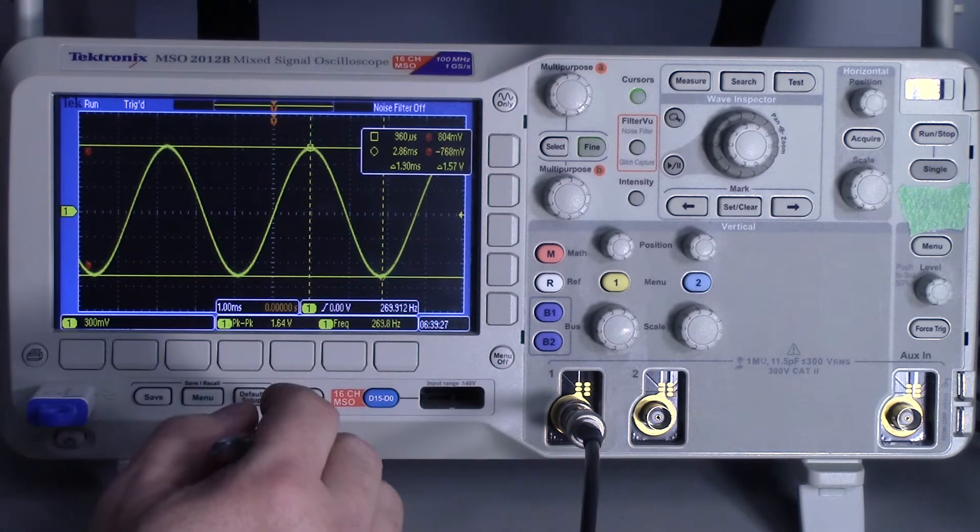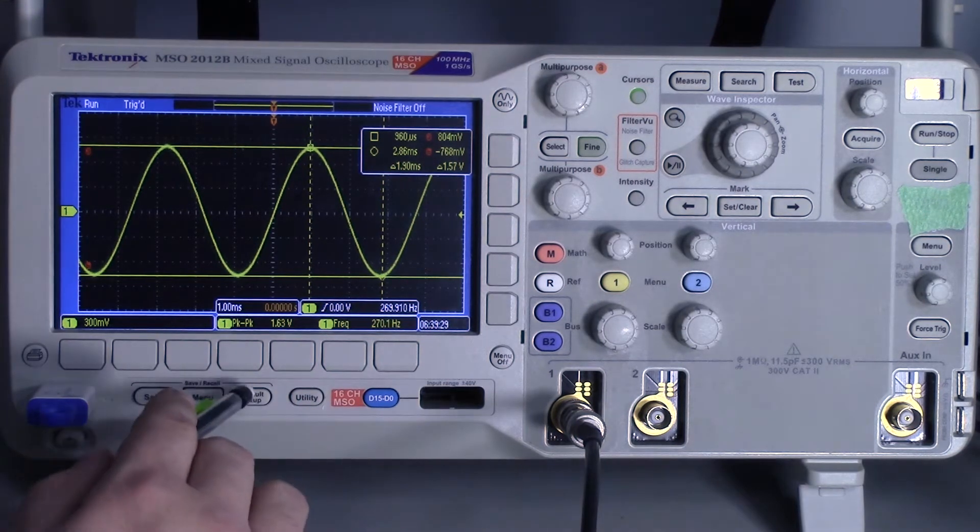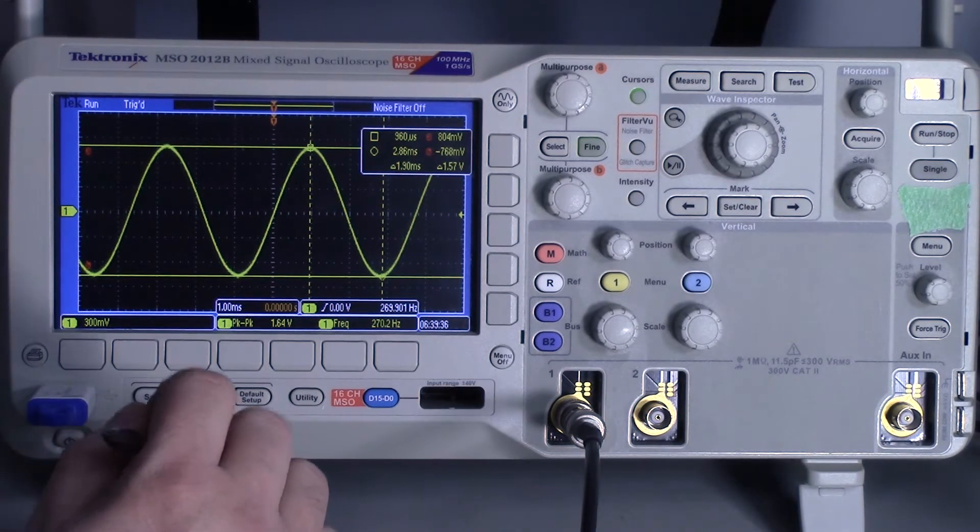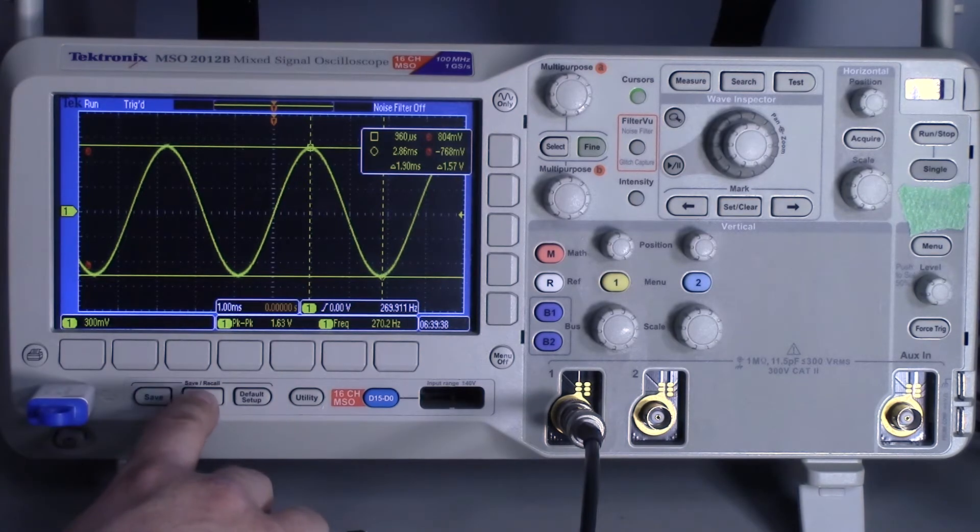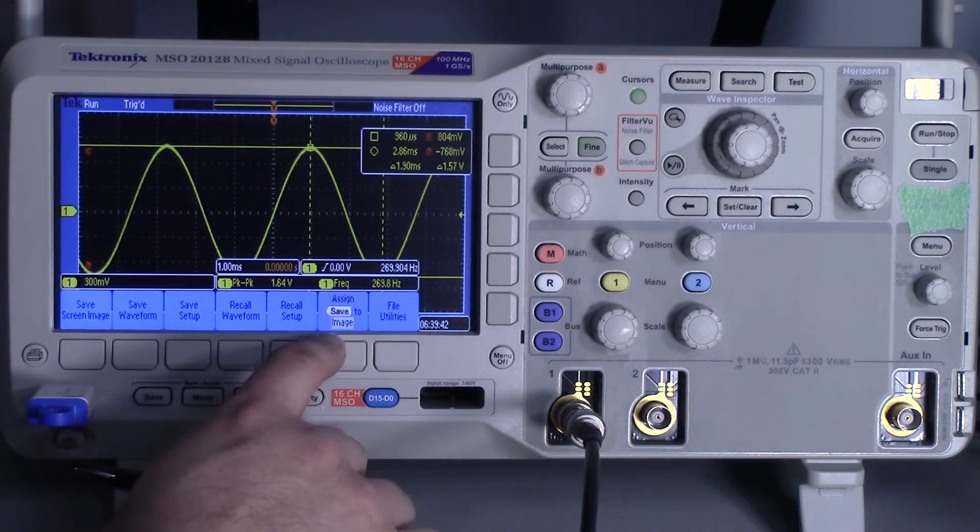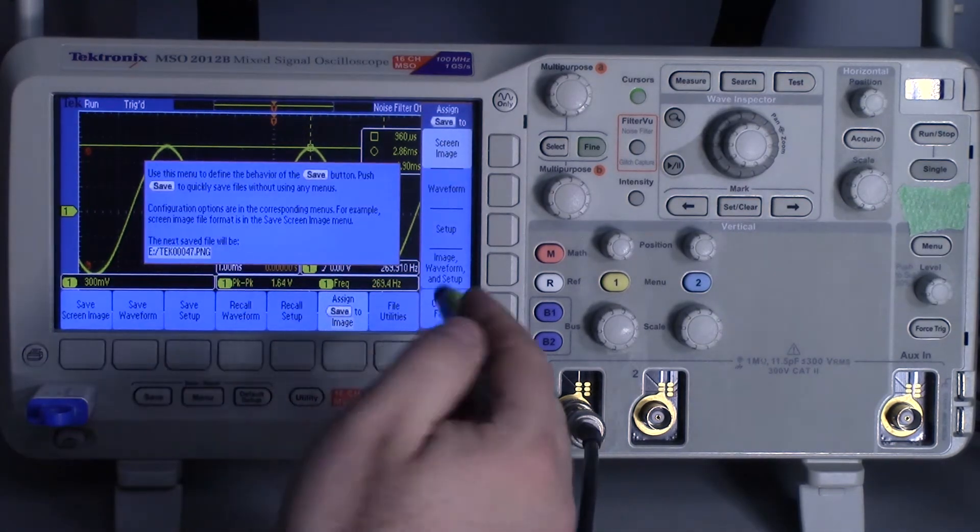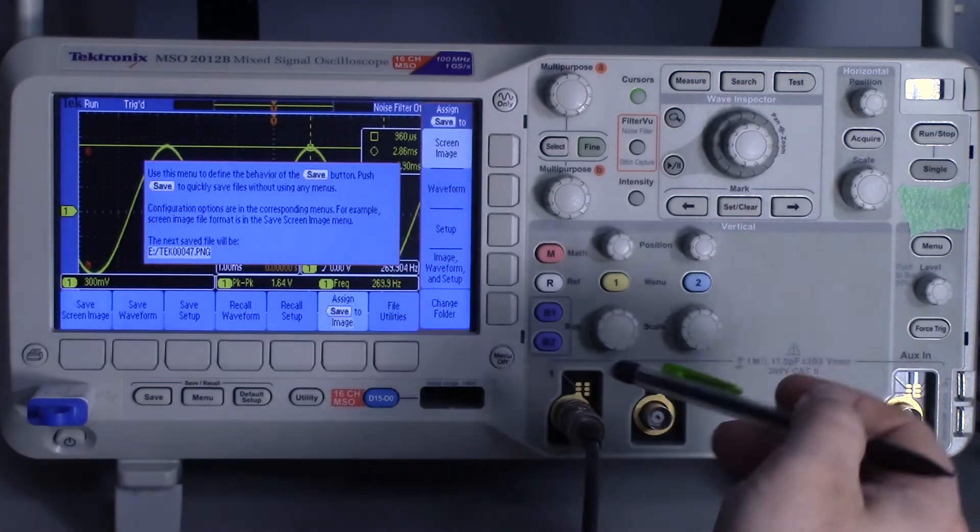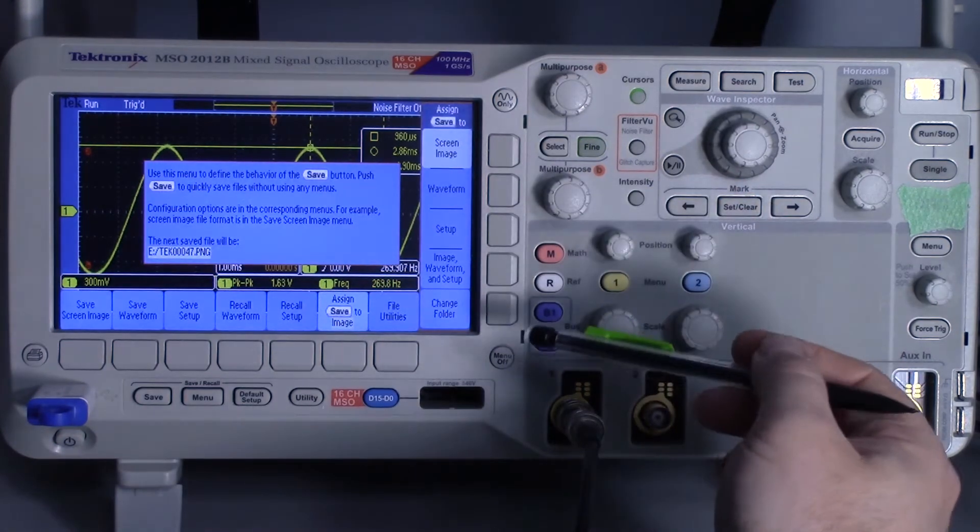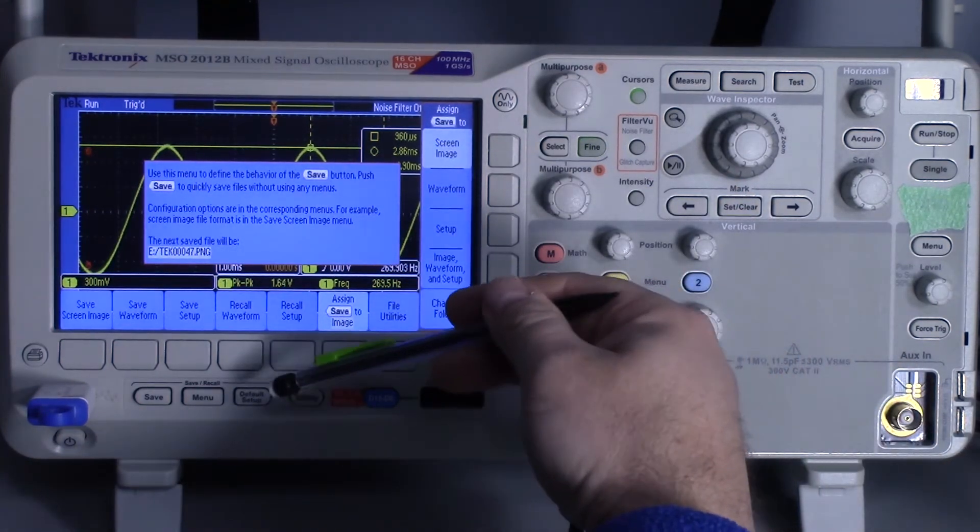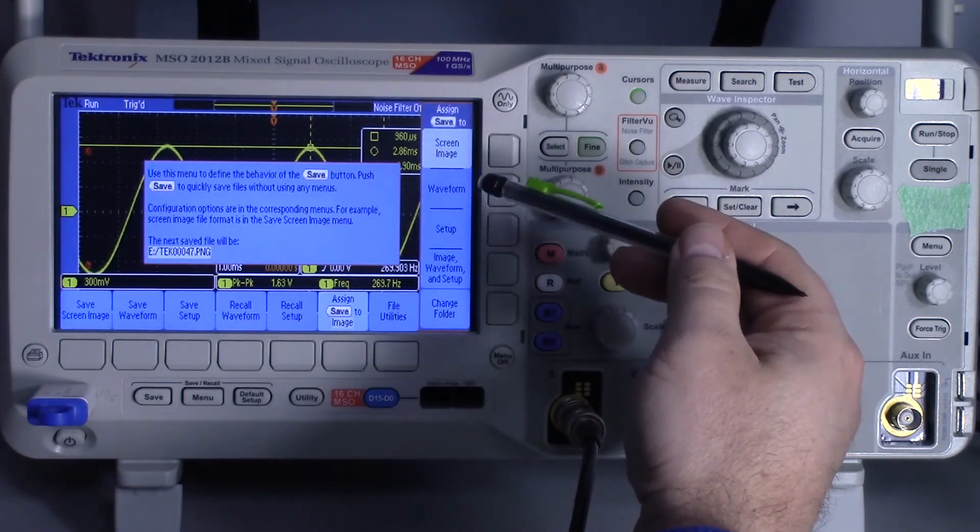The default setup button does not set this button to some kind of default, so you always want to go to menu and assign save to image. We can assign any of these three, or all three. I always recommend to make sure that you go at the beginning of the lab to hit your default setup, and then make sure you save what you want.